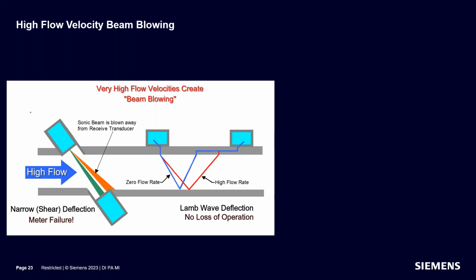What you do see here, though, is that, for example, the blue trace is a zero flow condition. So the beam crosses the pipe and comes back, travels down the pipe wall to the receiver. But when there's a high velocity flow, it takes the red path and it's getting blown further down the pipe. So the pipe travel is less. And again, because it's not a dispersive beam, it has no impact on the shape. The shape stays constant. Just the amplitude varies. And the amplitude is really secondary. And I have a great example of that here.